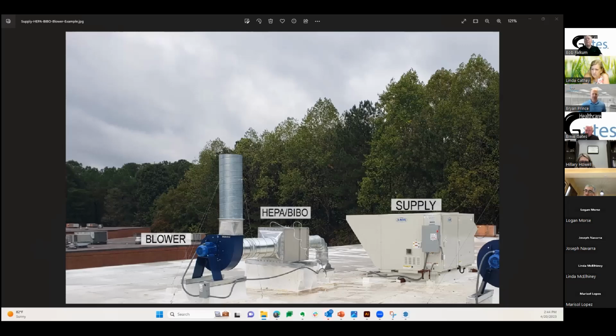Let me tell you the money maker, money breaker statement—I'm surprised I left it out of my slideshow because I get into this all the time. Old technology air handling systems use single stage compressors, where your thermostat sends a signal back to the compressor to start and stop on its cooling cycle. Humidity is only a byproduct of temperature control there, not an independent variable. That's your single stage DX system, which is on all of your commercial spaces now.